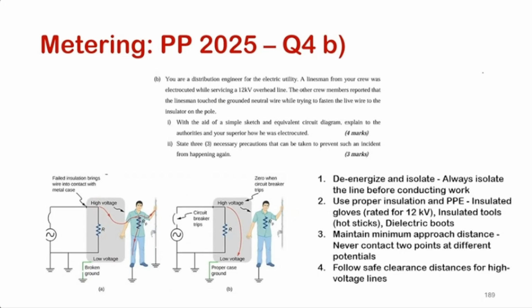So you have the line there, the 12 kV line, and this is your neutral, grounded. And he, inside here, touches the line. Here is our person. I remember he was working at a height, so he has a lower impedance compared to the ground. That's why he gets shocked. And that diagram could be drawn like this: the source will be a 12 kV source, the person, and that's how you get shocked.